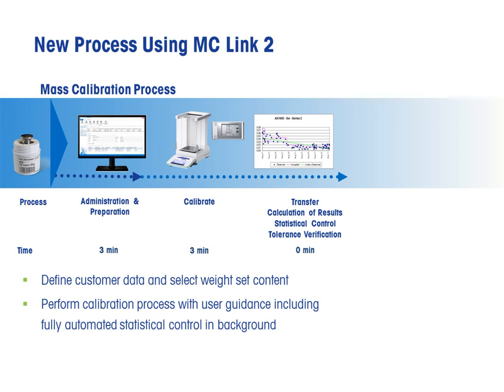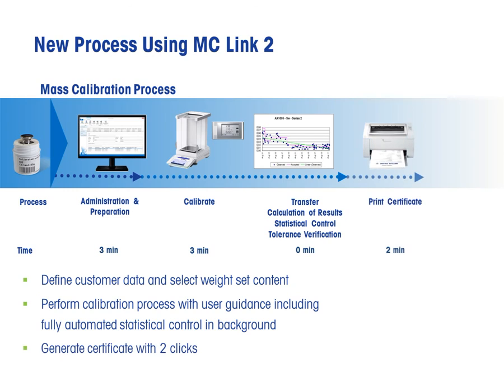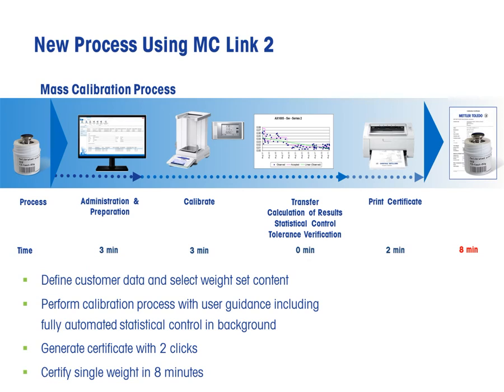In the background, all the statistical processing is performed in real time, and the user is alerted if limits are exceeded. Having printed the certificate, the calibration process is finalised. In total, one weight calibration, including printing the certificate, takes less than eight minutes.